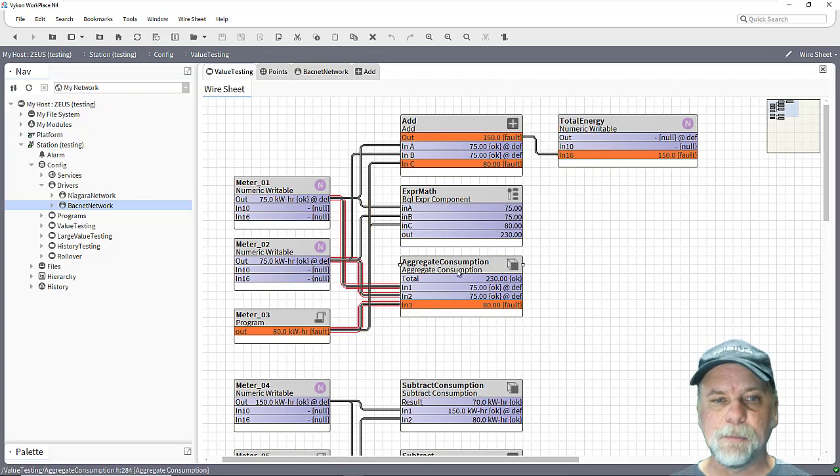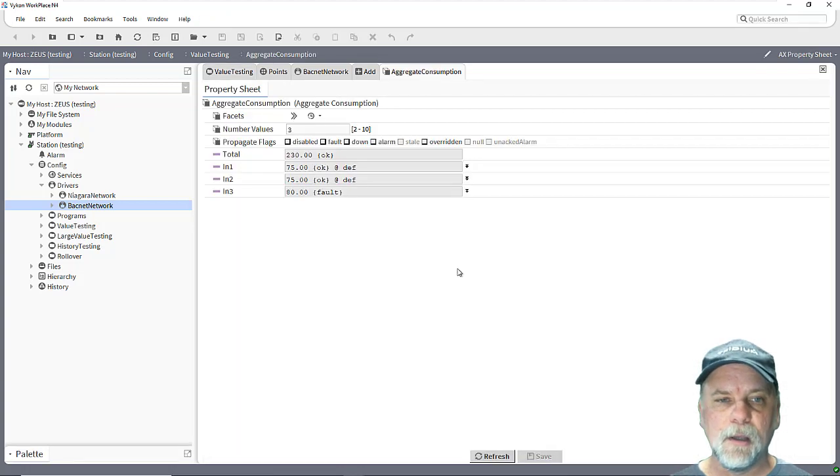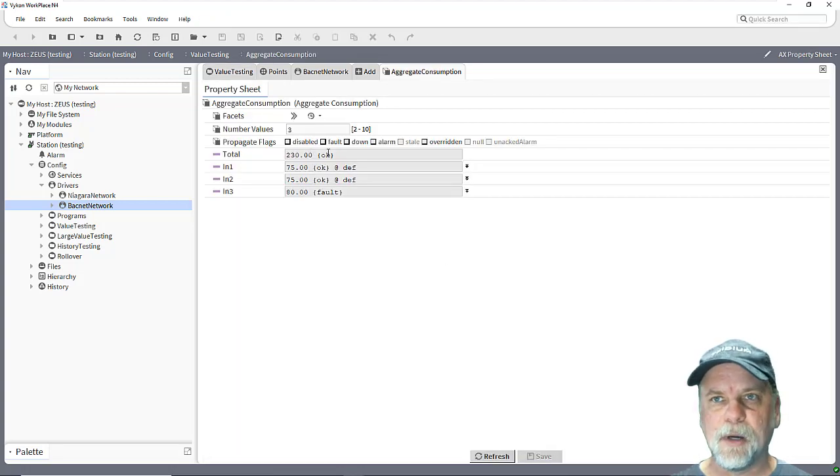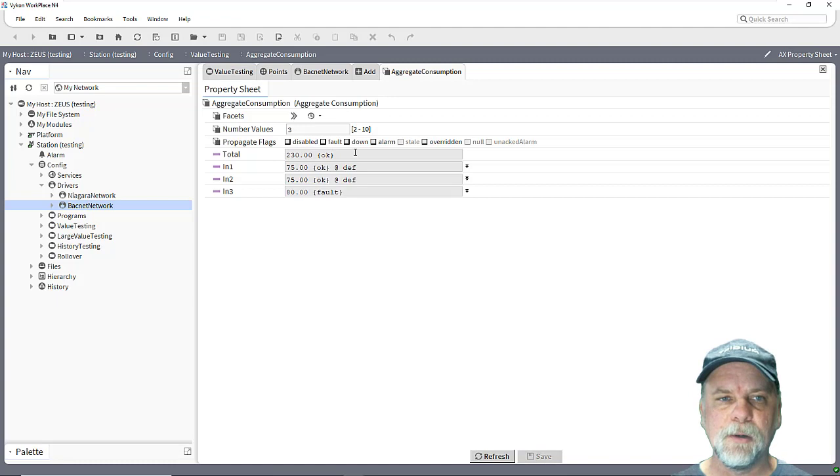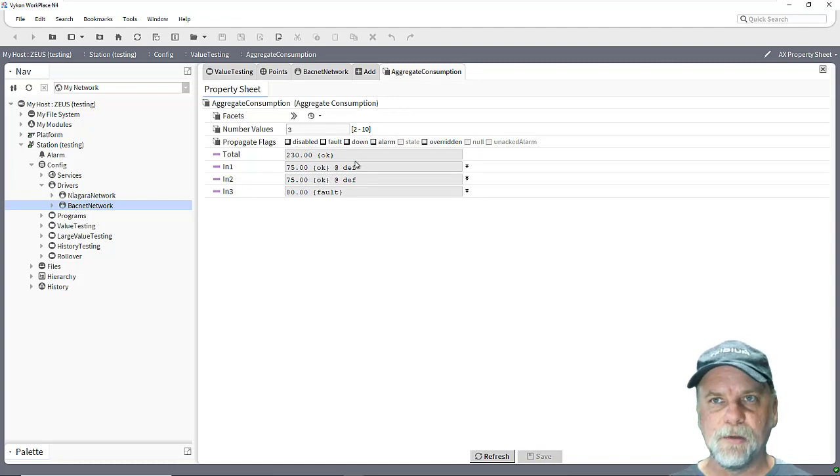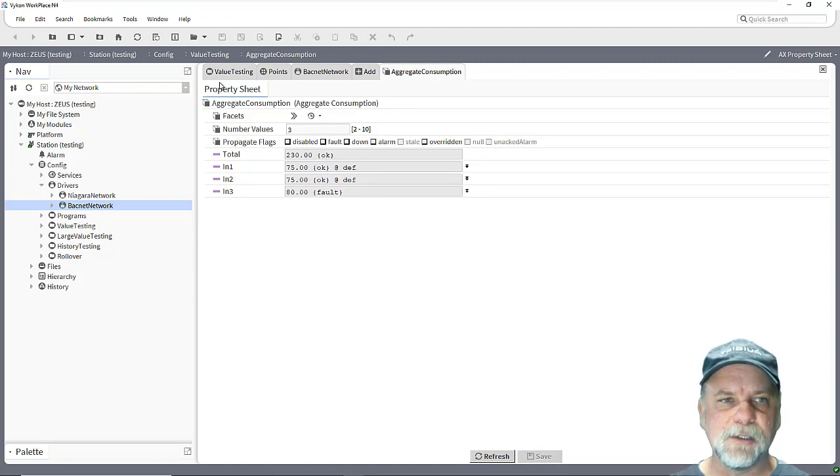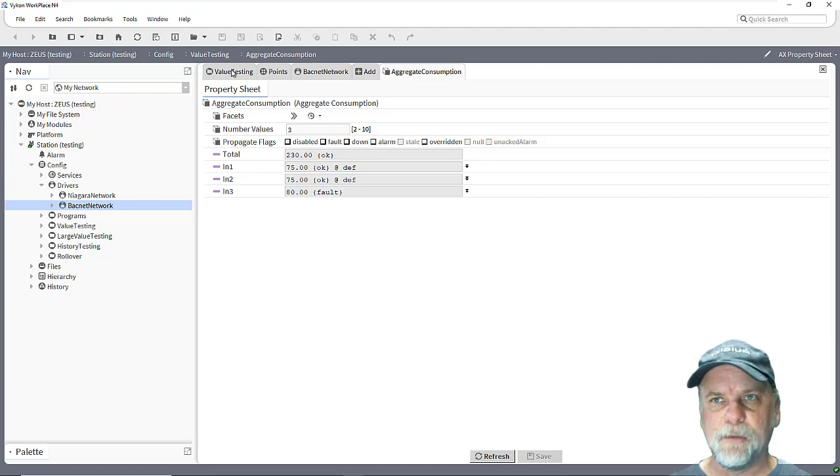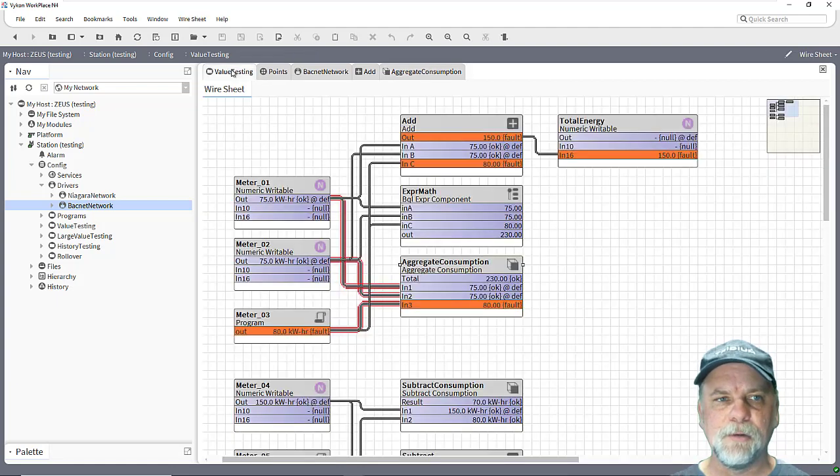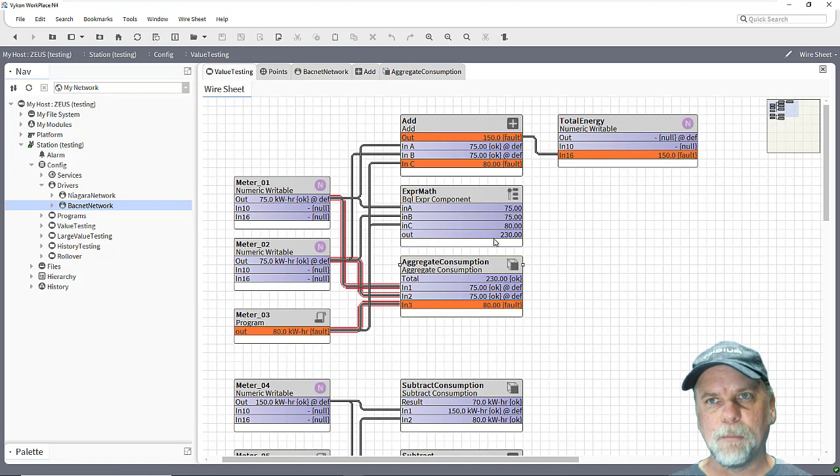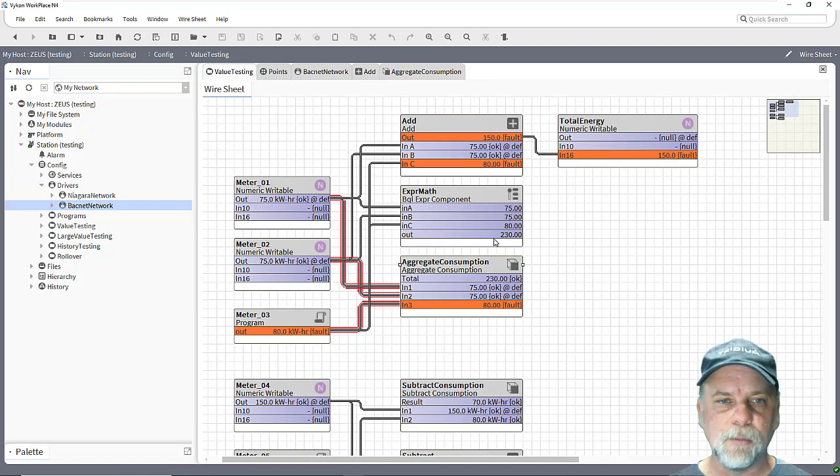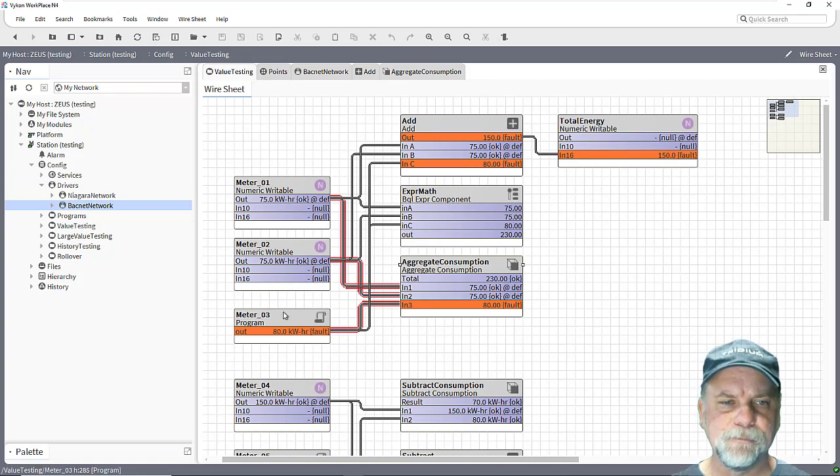And the aggregate consumption block also has a propagate flags property on it as well so we can certainly propagate those input statuses to give us some indication of that reliability, although in this case we're holding on to the last known valid value so maybe that propagating flags is not as important with the aggregate consumption block.